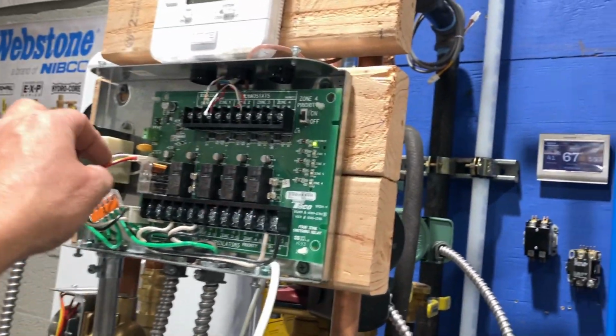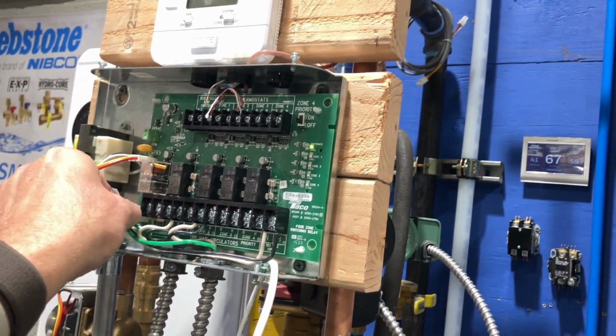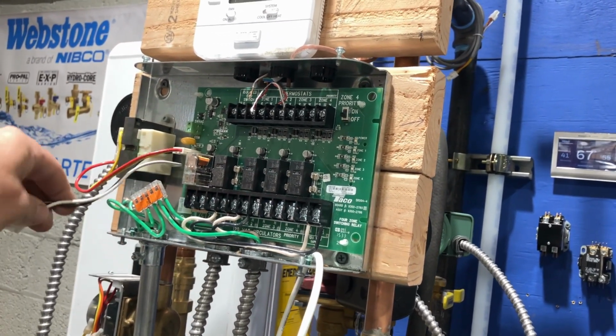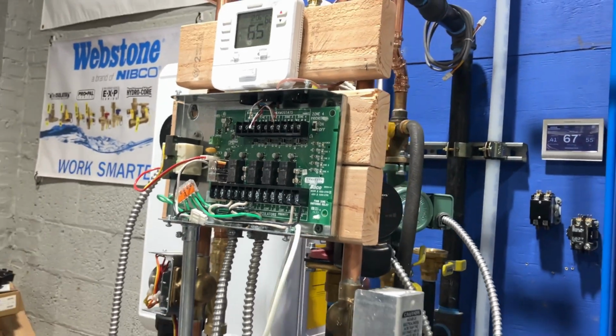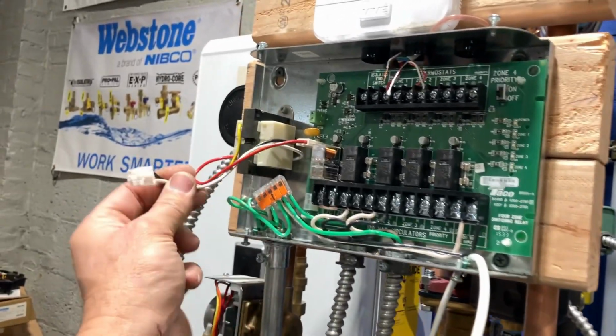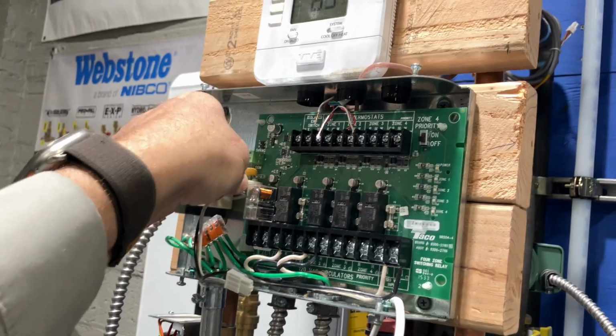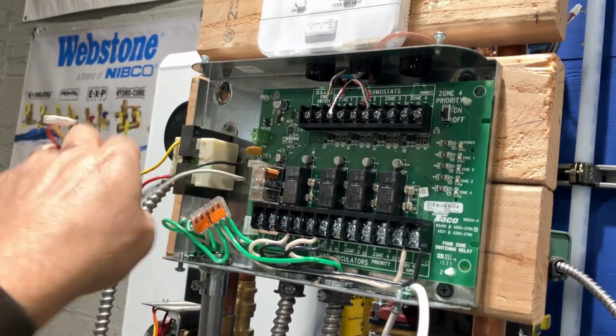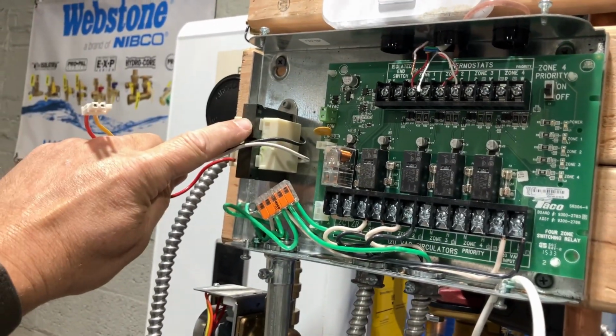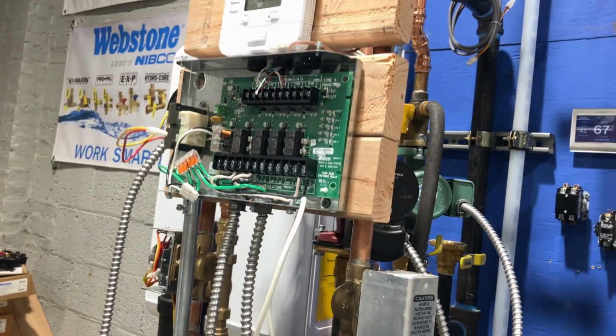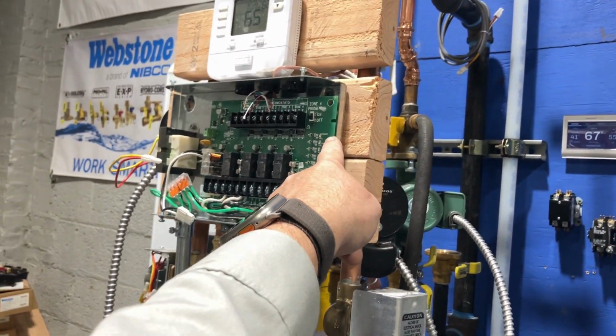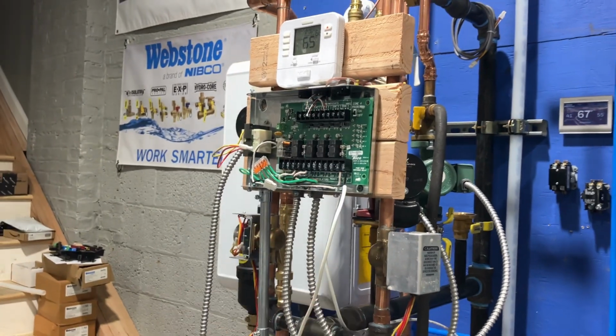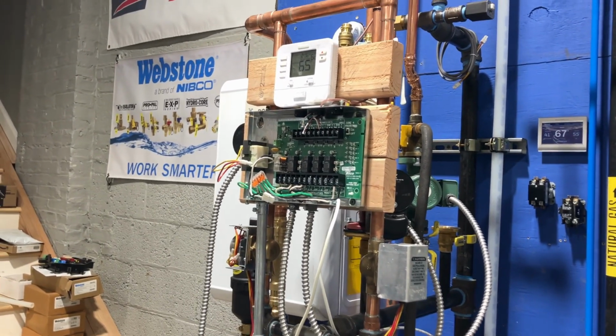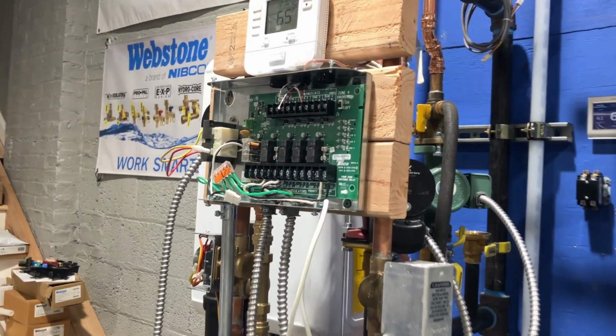Because there is a 24-volt circuit powering this control board. What I just did is remove the transformer from the equation, from this control. Now this transformer, which is sitting right here, is out of the equation. That green light is out, right? So when testing these switching relays, never assume anything. You always want to make sure you have power.